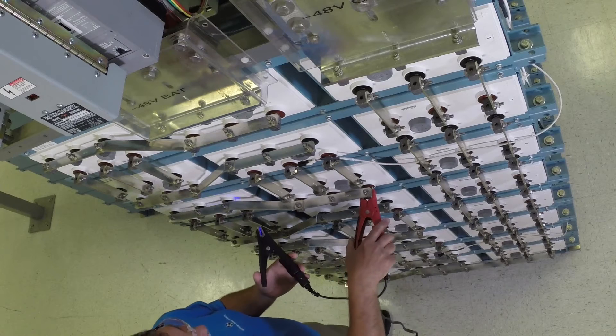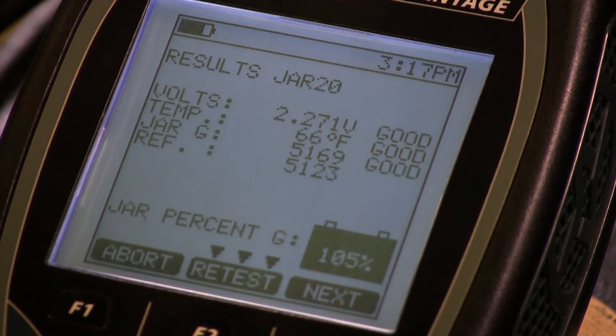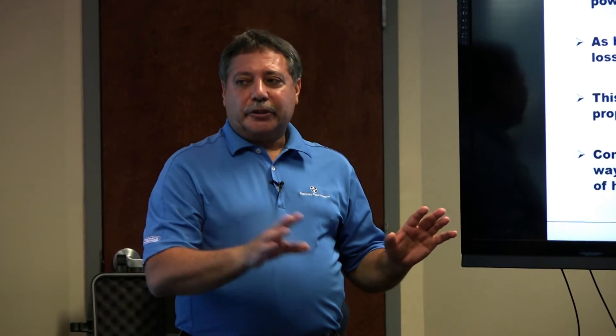Conductance is Midtronics' patented technology. It's a form of ohmic testing. You could have resistance, impedance, or conductance — Midtronics uses conductance. What conductance is doing is measuring the plate surface, the electrolyte that's in there, and the welds that are in there.